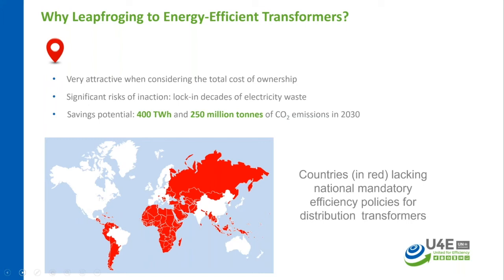So this is a very attractive proposition for the utility, for a product which has a life longer than 30 years. And the saving potential exists: 400 terawatt hours or 250 million tonnes of CO2 emission by 2030 for the countries where there is no regulation. You can see that countries in red are lacking national mandatory efficiency policies, and most of the African continent is included. Therefore, this opportunity is a low-hanging fruit for Mozambique, because today we are talking to the utility which owns more than 90% of the transformer assets in the country.